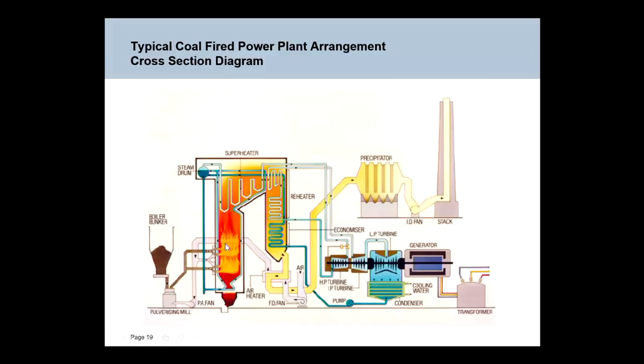And then the heat is given off in this furnace. The walls of the furnace are made up of tubes which have water in them. And then there are more tubes hanging in the gas path here which have steam in them. And the heat in the gas is given up to those tubes to give you superheated steam, right? The combustion gas then flows out through this air heater, up through, in this picture, a precipitator where you clean the dust and ash out of it, and then is ejected up the stack where hopefully it comes out looking fairly clean. Okay? In the meantime, the superheated steam comes out of the boiler into this HP turbine, into the IP turbine, LP, back into the condenser and round again. Okay? And that turbine is driving a generator here, which is connected electrically to a transformer, which connects you to the grid. So if you can go away with an understanding of that picture, you have a pretty good understanding of how a coal-fired power station works.